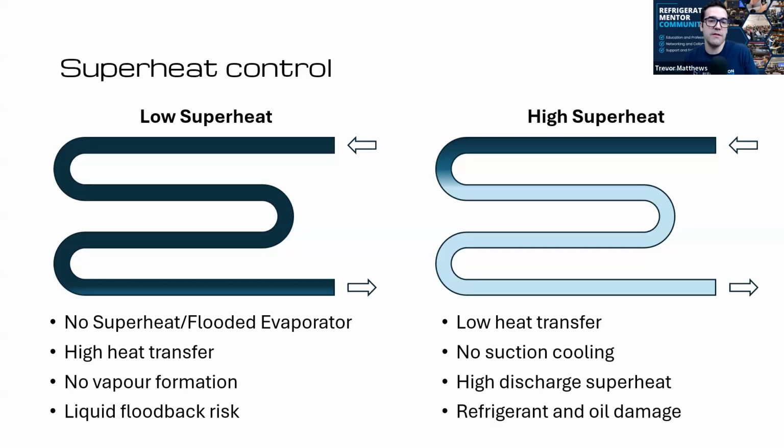Could that affect, if low superheat, could that potentially increase the temperature of a case if you ever had flooding, or would it drop the case? I'd like to drop the temperature. Can you elaborate on that too, when it is flooding, or that coil that is supposed to boil off, but it's all liquid in there?